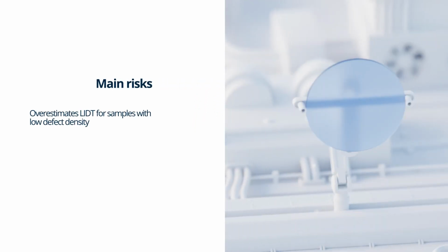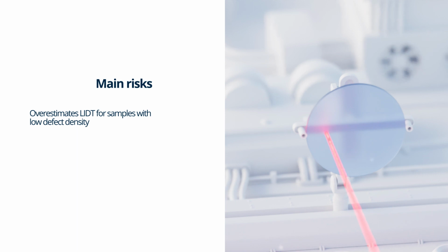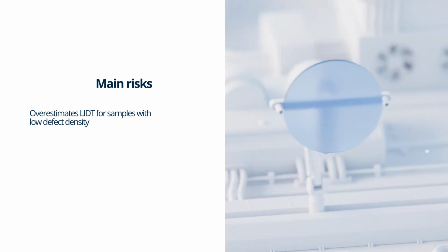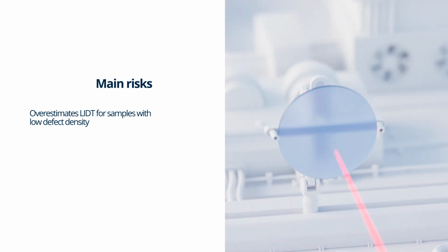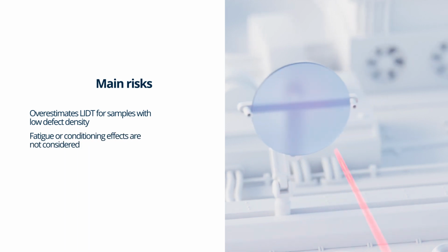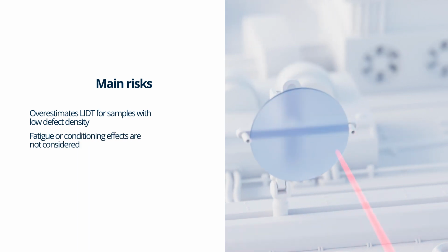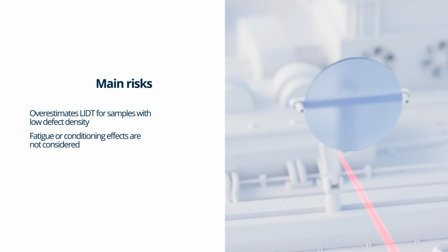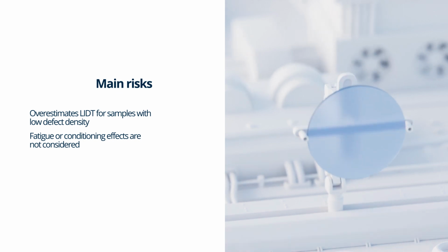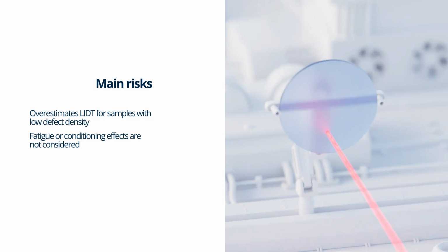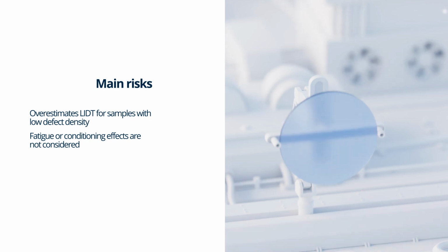However, no technique is perfect. One-on-one procedure could overestimate LIDT in cases of low defect density or produce non-repeatable LIDT values. Fatigue or incubation effects are also not considered here. Other test procedures must be chosen when investigating multiple or long-term irradiation effects, using one-on-one LIDT as a good reference.